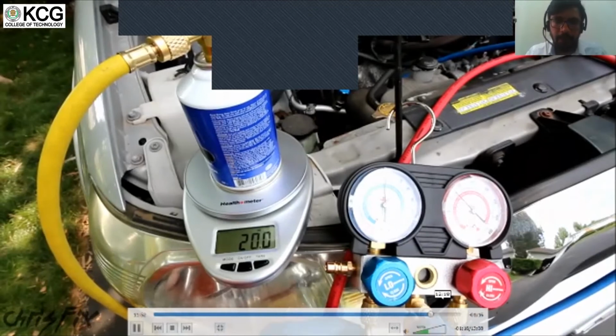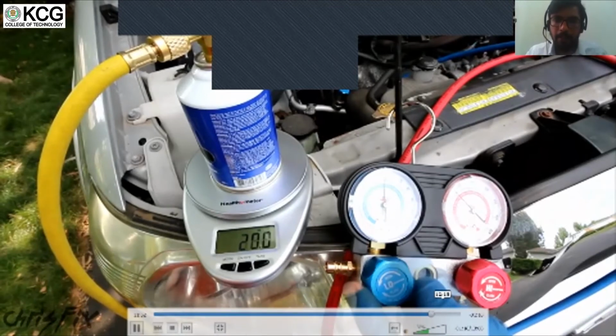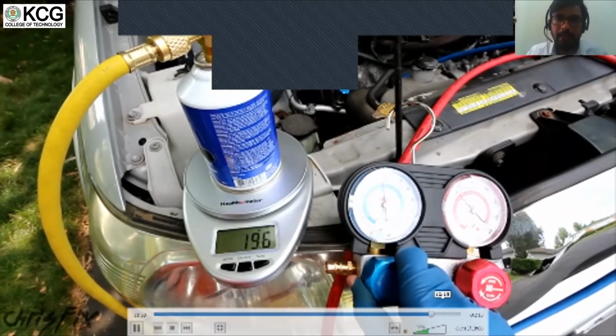After a little, we could open up the valve the rest of the way to get the can down to 10 ounces. Okay, at this point, we're almost at 10 ounces, and I'm going to close this valve up. All right, charging is complete. Now you have to disconnect the circuit, and I think this will be good for your refrigerant system. So back to our PPT now.